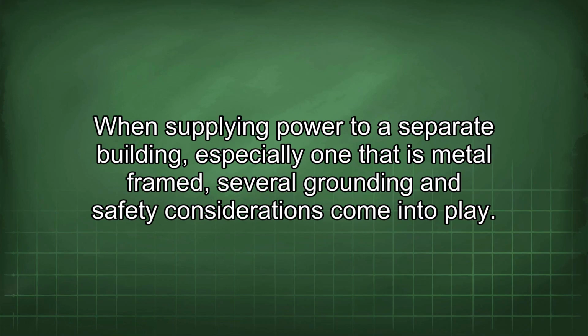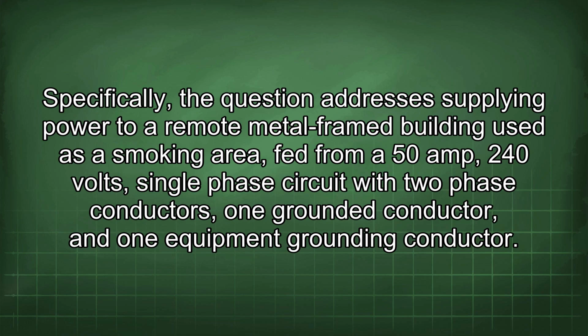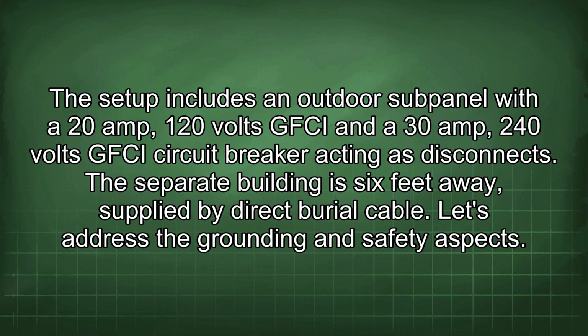When supplying power to a separate building, especially one that is metal-framed, several grounding and safety considerations come into play. Specifically, the question addresses supplying power to a remote metal-framed building used as a smoking area fed from a 50 amp, 240 volts, single-phase circuit with two-phase conductors, one grounded conductor, and one equipment grounding conductor. The setup includes an outdoor subpanel with a 20 amp, 120 volts GFCI and a 30 amp, 240 volts GFCI circuit breaker acting as disconnect.